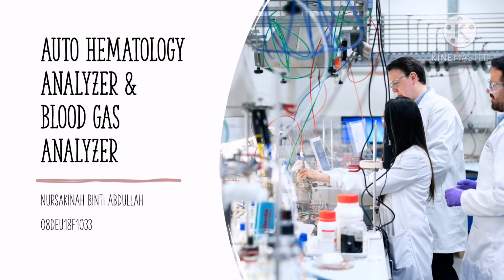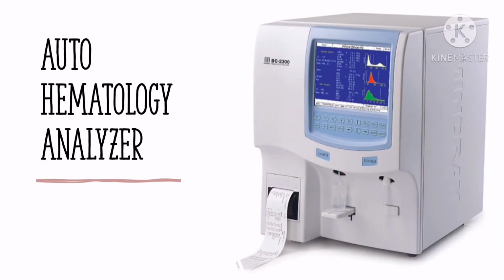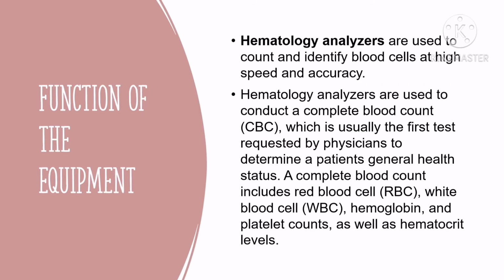The next equipment that we're going to be talking about is the auto hematology analyzer and the blood gas analyzer. Auto hematology analyzer, function of the equipment. Hematology analyzers are used to count and identify blood cells at high speed and accuracy. They are also used to conduct a complete blood count, which is usually the first test requested by physicians to determine a patient's general health status. A complete blood count includes red blood cell, white blood cell, hemoglobin, platelet counts, as well as hematocrit levels.